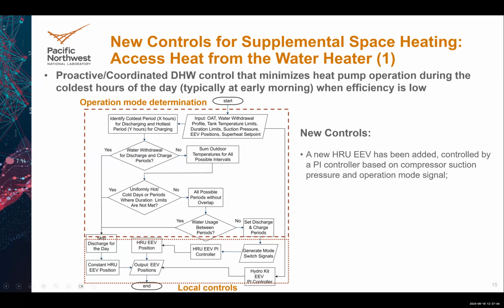the cold weather conditions. The second thing is, instead of a regular controller, for example an air to refrigerant heat exchanger, usually you control the EV using a superheat set point like 5 to 10 C, right? But for this particular scenario, we have the water to refrigerant heat exchanger. So this EV is adjusted via a PI controller, but we maintain a higher superheat set point. For example, we use 40 C. So in this case, you are able to absorb the heat from the tank.